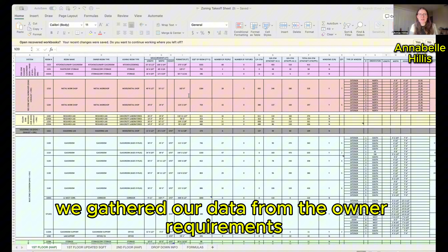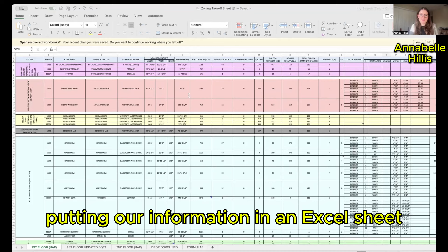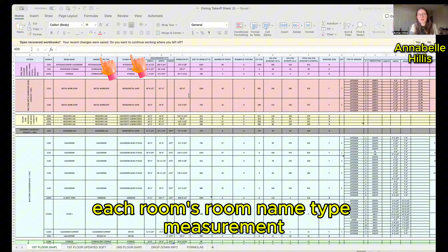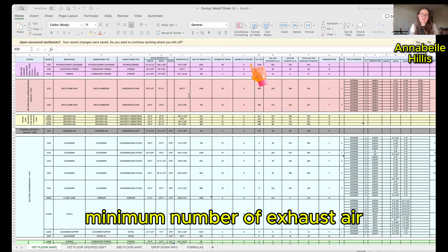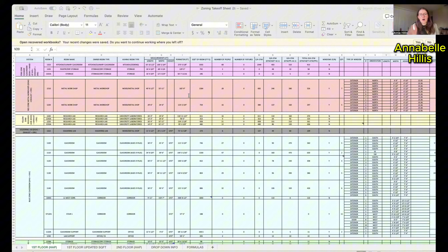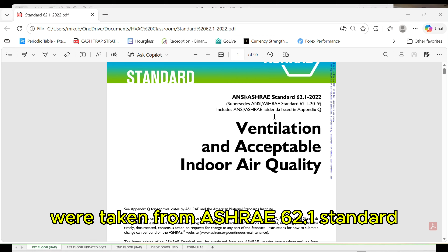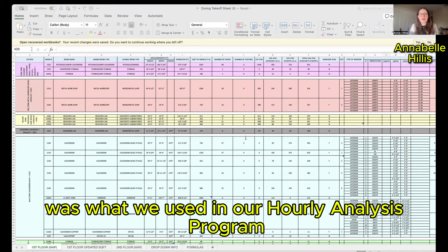To organize our information, we performed a takeoff. We gathered our data from the owner requirements and from the drawings provided, putting our information in an Excel sheet. In here, we have rooms organized by zone and marked each room's room name, type, measurement, number of people, fixtures, minimum number of exhaust air, outdoor air, as well as exterior window dimensions and orientation. Our values for exhaust air, outdoor air, and number of people were taken from the ASHRAE 62.1 standard, which provided the necessary formulas for each. The data we collected in our takeoff was what we used in our hourly analysis program, aka HAP, to calculate building load and energy.